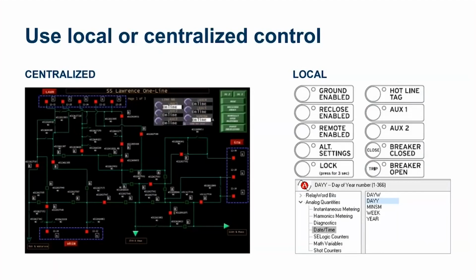You can also create logic in the relay. So you can enable or disable reclosing only during a specific time of the year or specific days of the year. You can use these analog quantities or logic in the relay to enable or disable reclosing only during a particular time of the year. So local and centralized are both good, but in certain cases, we might need dynamic control over reclosing, so that I can enable and disable reclosing based on system conditions or where the fault is. So we're now going to talk about how to dynamically control reclosing.